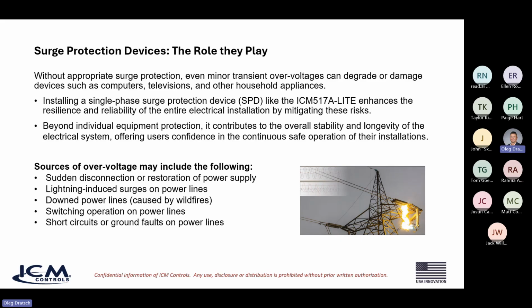A surge protection device, like I mentioned, there's all sorts of different ways that this can happen. But basically, there's more electricity on the grid. A lot of these new HVAC units, new furnaces, have control boards on them with microprocessors, and so this increases the risk of damage from a transient voltage surge. Any type of event that I mentioned earlier, down power lines, lightning, short circuits, ground faults, turning the power on and off, power outages, all those different types of things can cause a surge that could damage or even destroy a control board in your HVAC unit, your furnace. It could be really any major appliance.